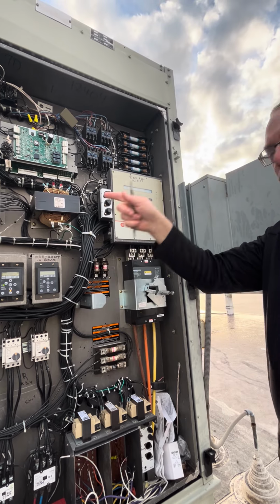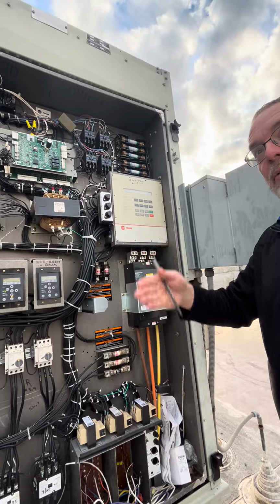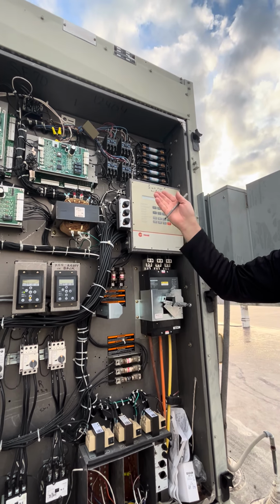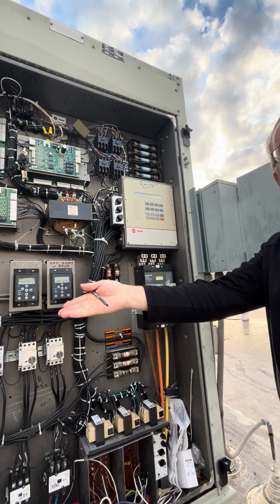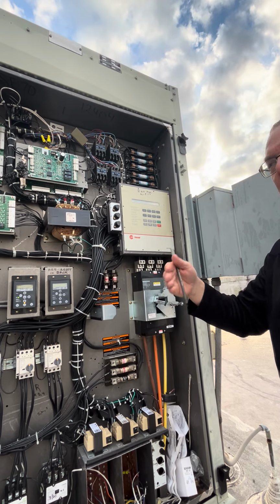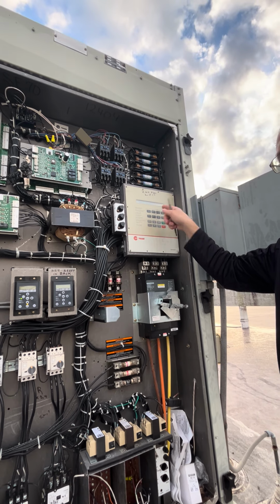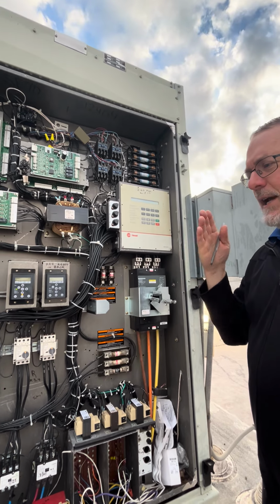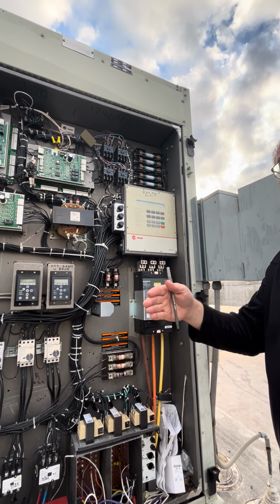Okay. So now the unit will start the cooling and start staging compressors up, those K9, 11, whatever those relay numbers are. Right. And bring on the cooling because the unit has its own discharge air sensor. Sure. And it wants to make 50 degrees. Right. Because that's what we're calling for. So we're at 74. We bring on one stage of cooling, two stages, maybe it takes all four stages to get to 50 degrees. Right.